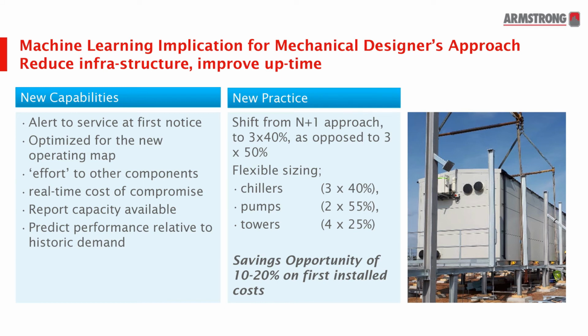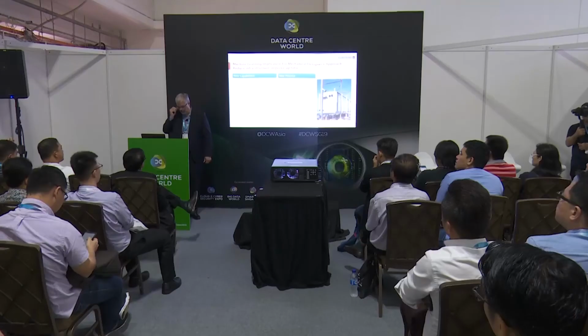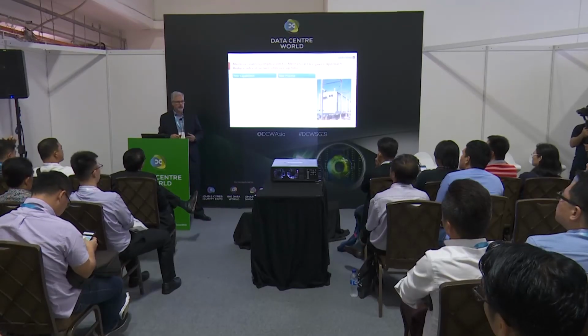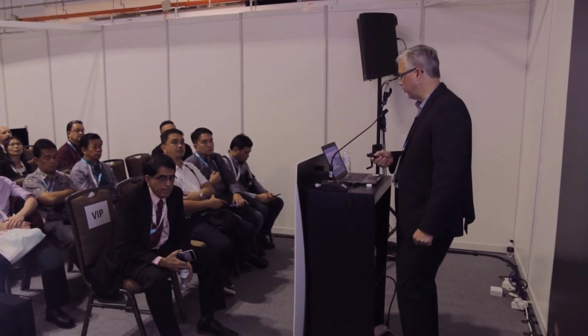We'll be able to shift the amount of effort. If there's degradation on the cooling towers, we're able to shift the effort to the chillers and the pumping system. This brings new opportunities for more resilience and availability through intelligence, as opposed to the brute force approach used with heavy carbon footprint N+1 and 2N designs, giving us the opportunity to leverage different combinations of equipment, such as two times 55% pumps and three times 40% chillers, while still having an operating sequence that works in a very robust manner.